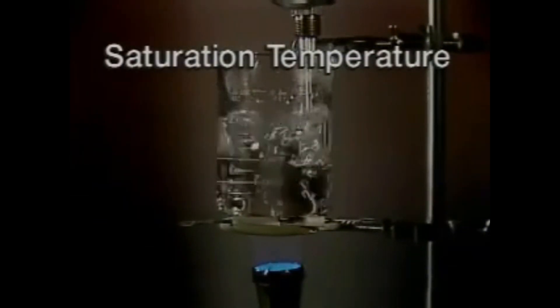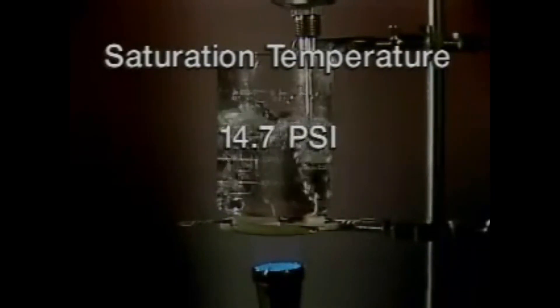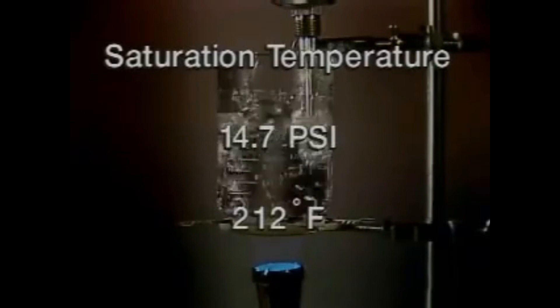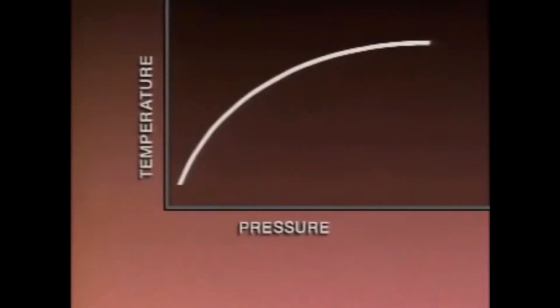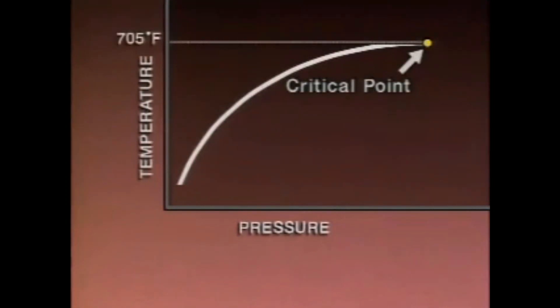At any given pressure, there is a corresponding temperature at which water will boil. This temperature is called the saturation temperature. For example, at standard atmospheric pressure, which is 14.7 PSI, the saturation temperature of water is 212 degrees Fahrenheit. When pressure increases, the saturation temperature also increases. At 1,000 PSI, the saturation temperature of water is 545 degrees Fahrenheit. When the saturation temperatures for water at different pressures are plotted on a temperature versus pressure chart, a line is formed showing the relationship between saturation temperature and pressure. However, this relationship only holds true up to a certain point. That point, called the critical point, is 705 degrees Fahrenheit and 3,206 PSI.